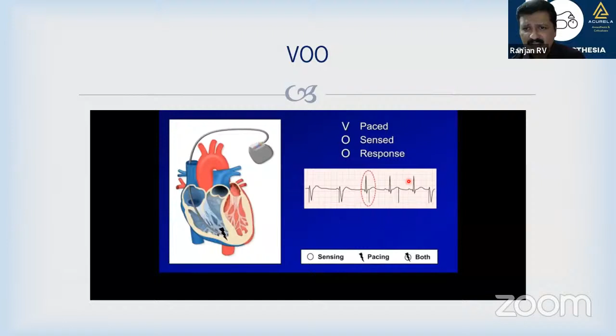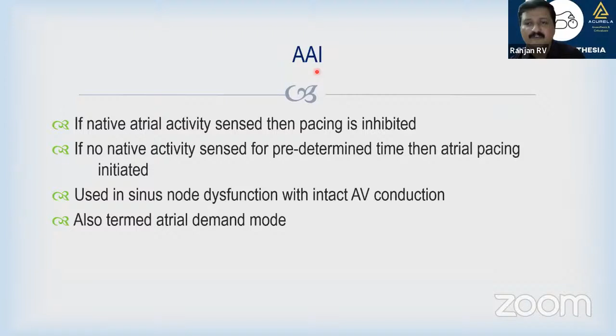The other one we should be aware of is AAI. As I told you, the first letter is the chamber which is paced, the second is the chamber which is sensed, and after sensing, the response is the third letter. Here the atrium is paced, the atrium is sensed, and if there is an atrial activity, it inhibits the pacemaker from sending any electrical activity to the chamber to be paced. This is the most common one used for sinus node dysfunction. When AV conduction is intact, we use AAI mode.